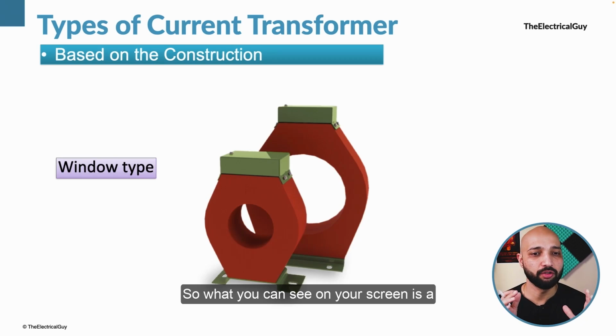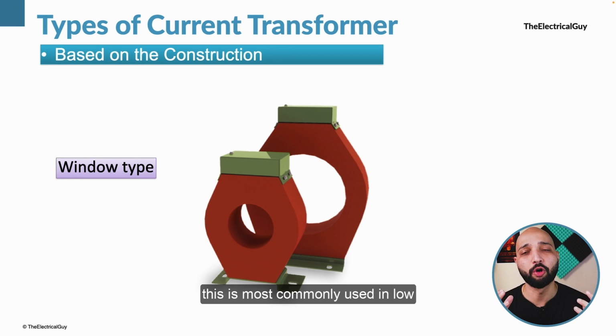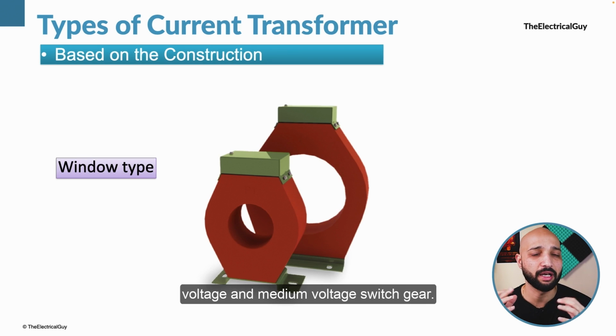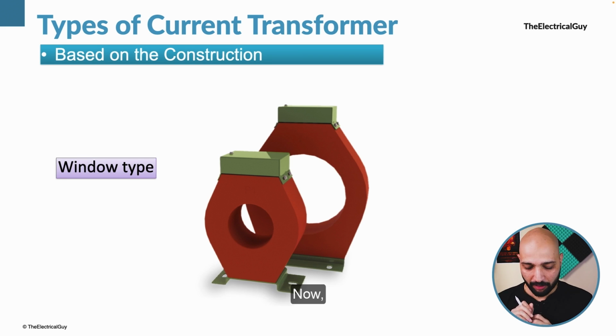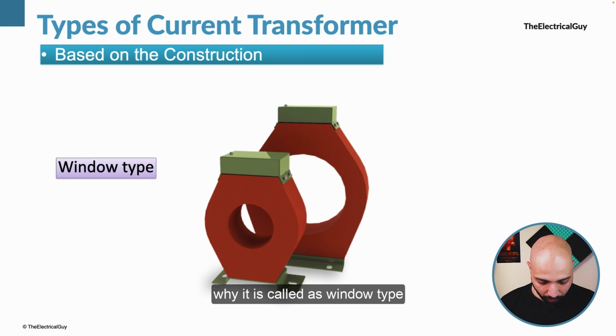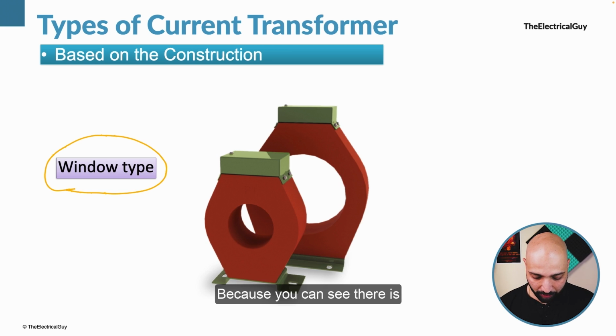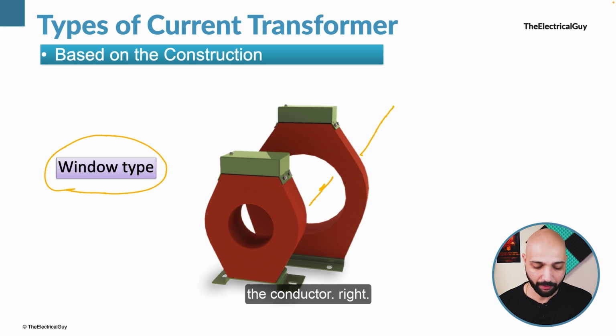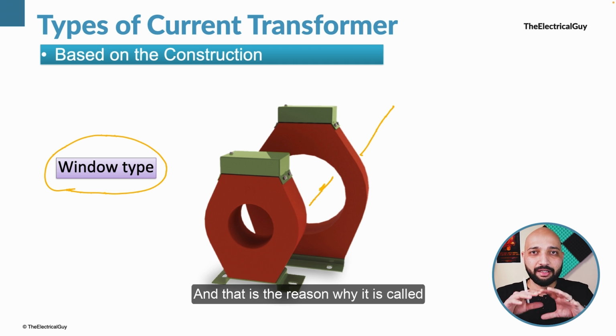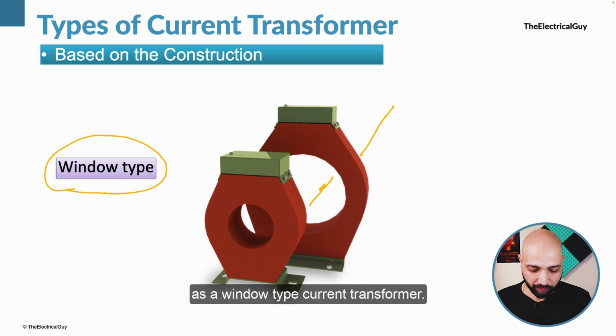Now let us start with the type of current transformer based on the construction. What you can see on your screen is a window type current transformer. Now this is most commonly used in low voltage and medium voltage switchgear. Why is it called a window type current transformer? Because you can see there is a window provided here, and through it you have to pass the conductor, right? And that is the reason why it is called a window type current transformer.